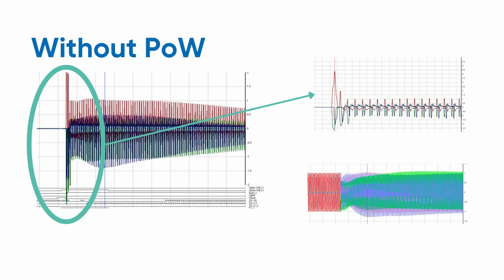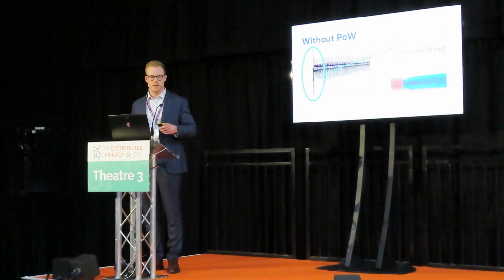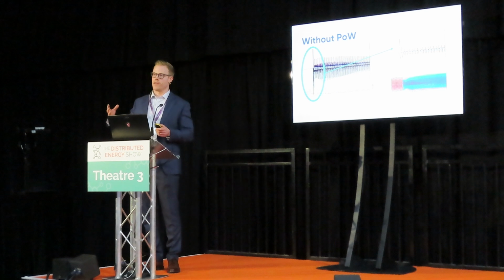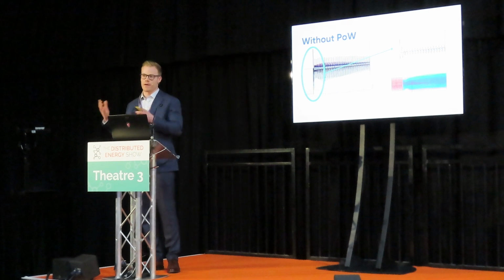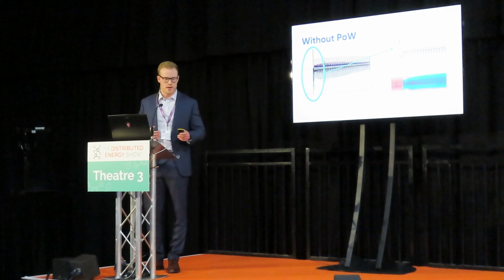You can see there that you have that sharp initial inrush current, and then the bottom graph just there, that's the voltage. So as you can see, the minute we energize, the voltage has a massive collapse, which would obviously be way out of the P28 limits. This operation was actually done on a diesel generator mini grid package. So don't worry, it wasn't actually a P28 non-compliant operation. So we were doing that to do the commissioning, so all the turbines are ready to go onto the real DNO without causing these types of disturbances.